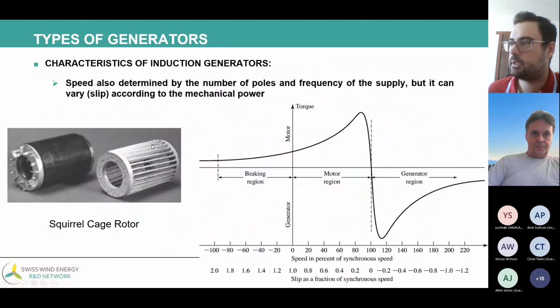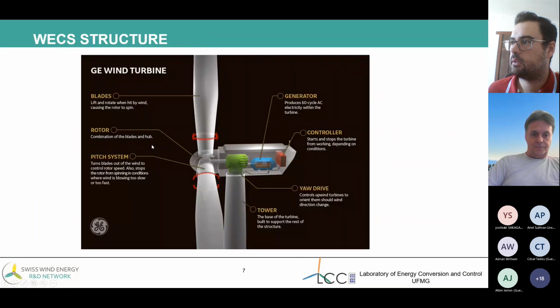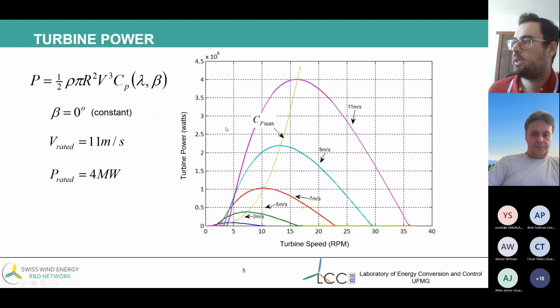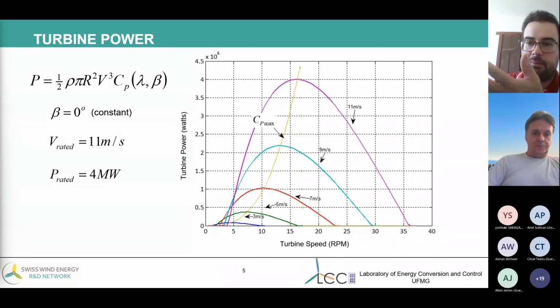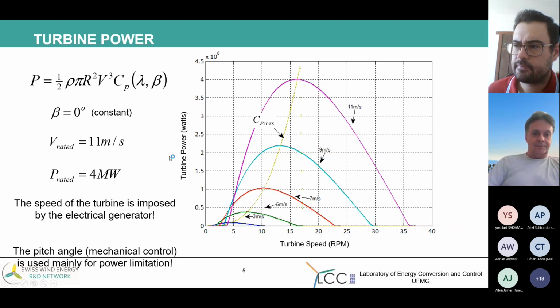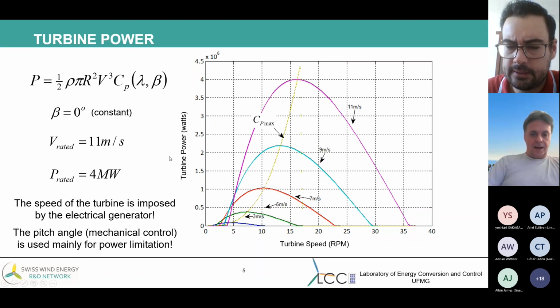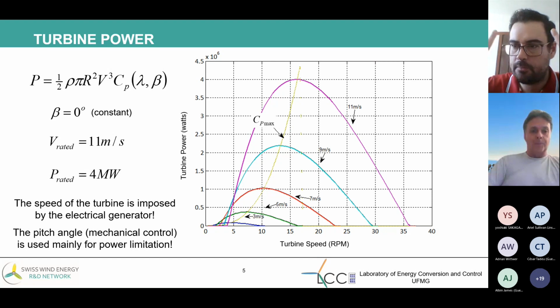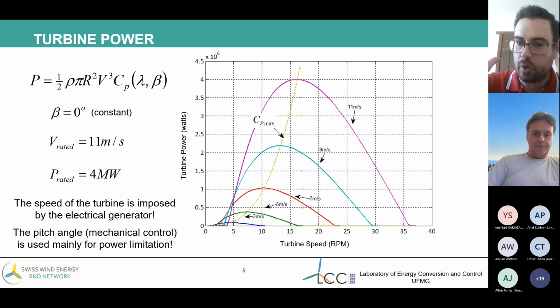Here we are changing the rotational speed to reach the maximum efficiency. Okay, so it is a mechanical action changing the rotational speed. The action of the electrical control is to change the rotational speed. So probably taking an action on the gearbox or something mechanical inside the turbine to do that, and not by the wind. No, the gearbox is fixed. It's electrical control.